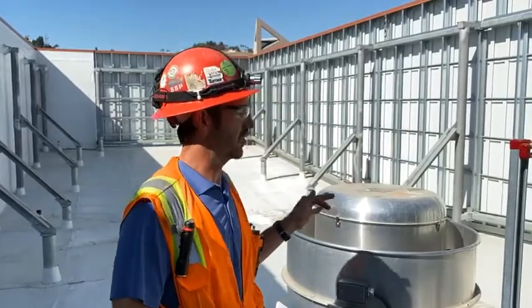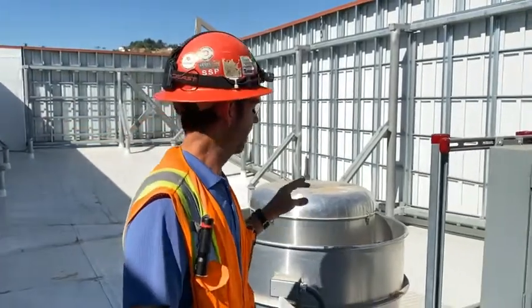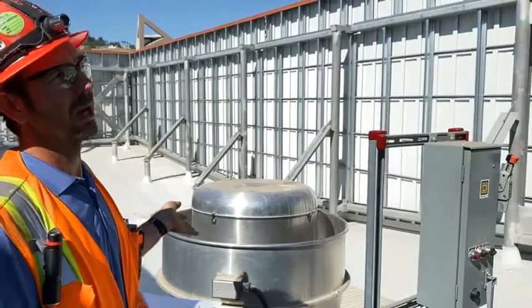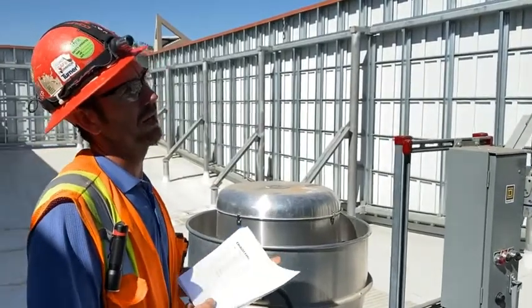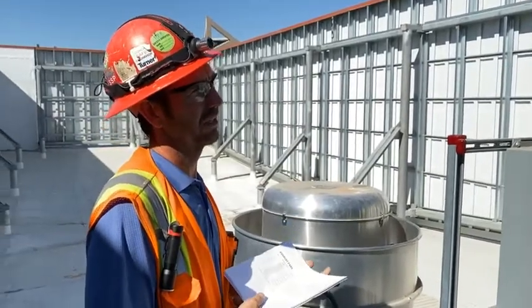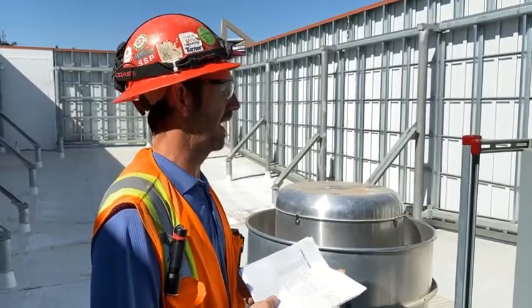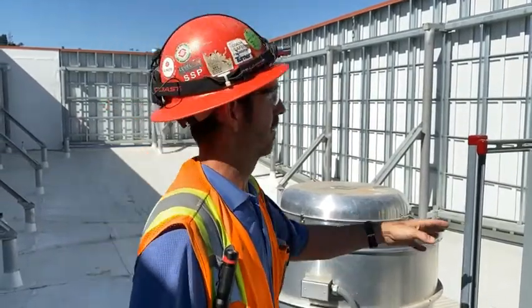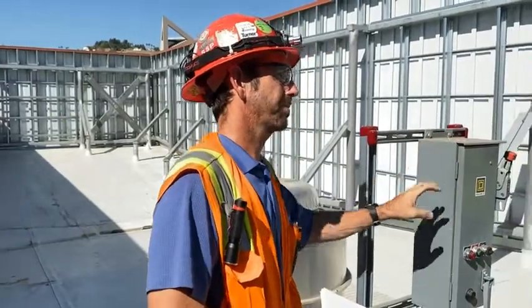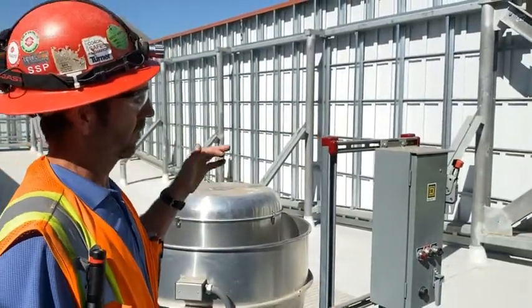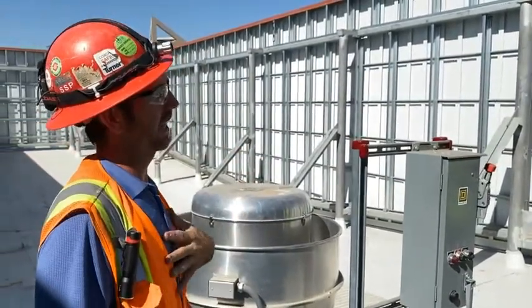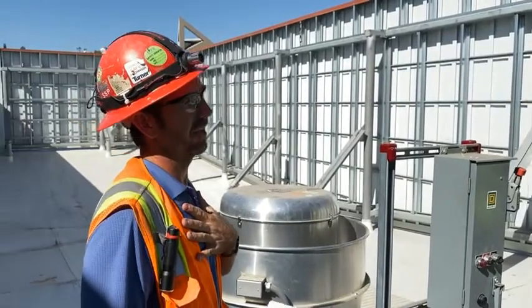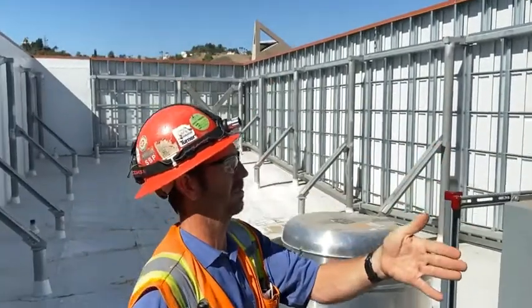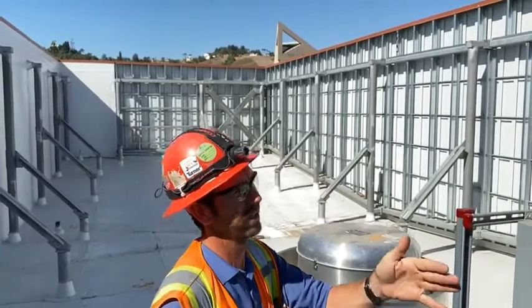This fan right here is controlled off the Ansul system as well. There could be a push button, or it might just be off temperature. The Ansul system was provided by the electricians. Same with the starter right here. The only device to turn on a fan that the mechanical contractor, AO Reed or ABET contracting, provided was the VFD that we spoke about yesterday that's on exhaust fan 1D.